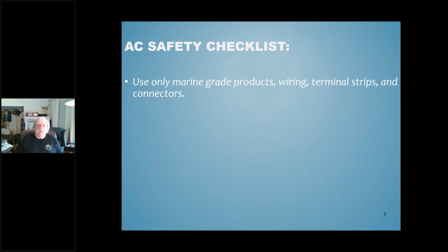Use only marine grade products, and I'm referring to the wiring and things like terminal strips and connectors. In terms of light switches and AC receptacles, the gear you're using is for all intents and purposes the same equipment that gets used in a residential or in some cases business or commercial application. I realize that companies like Marinco sell what they refer to as a marine rated receptacle, but they're really not very different from what you could buy at Home Depot, quite frankly. And I'll talk more about this in a little while because it is one of the potential areas where we can run into problems based on the wire that we use.